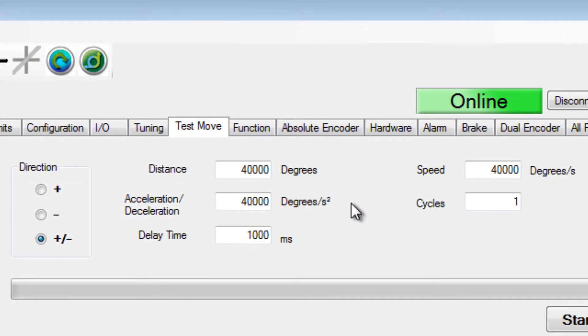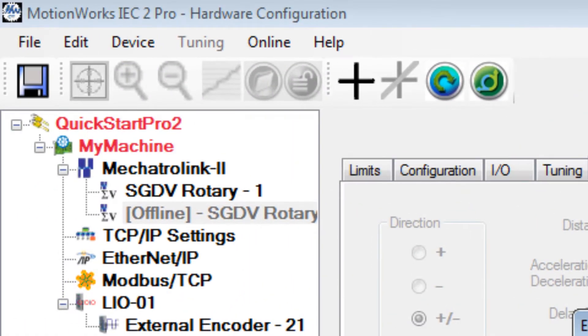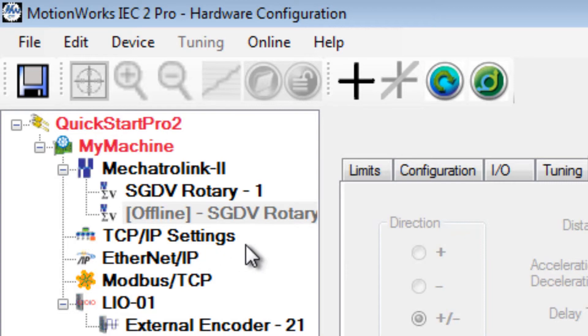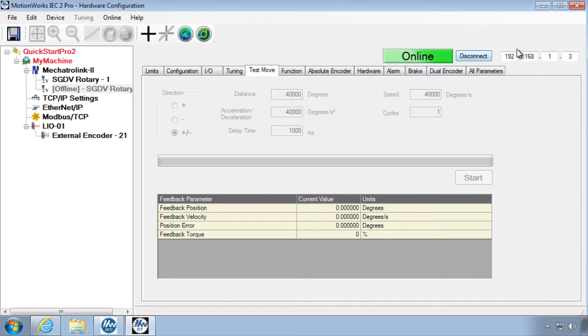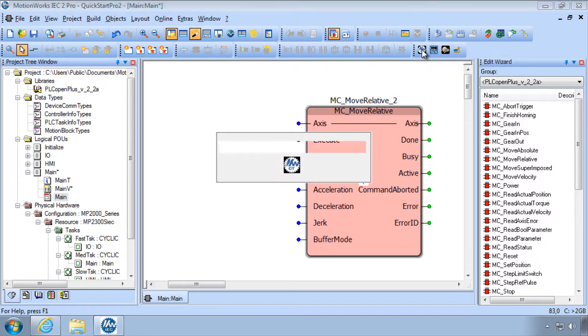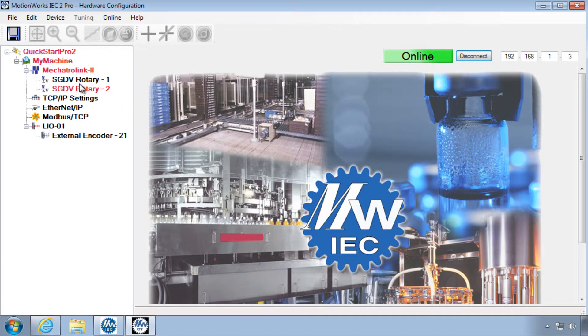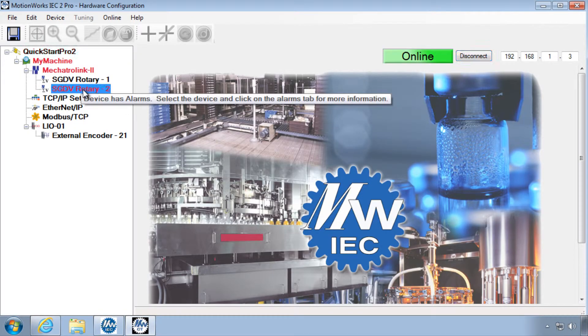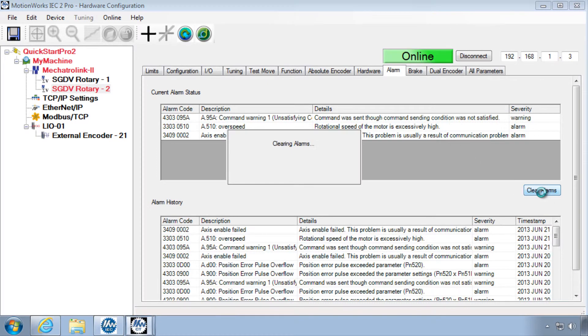If you're in the test move and the axis doesn't enable, it may be because that axis does have an alarm, and the axis may go offline as you see here in the tree. In this case, you'll have to close and reopen the hardware configuration and connect again, and go to that problem axis and troubleshoot the alarm under that alarm tab. Often you can just clear the alarm.